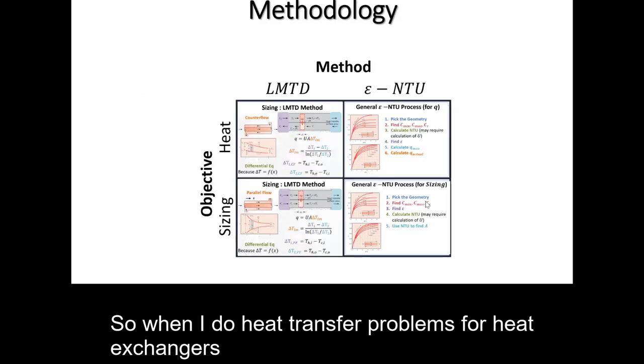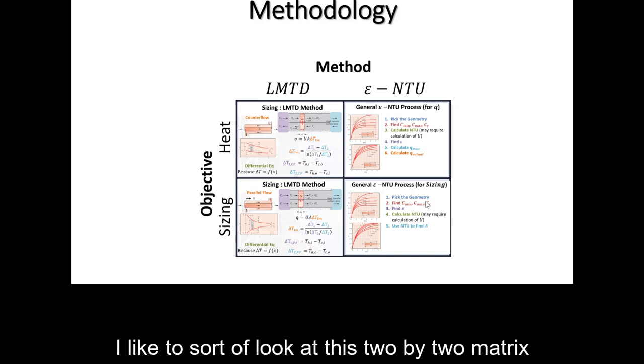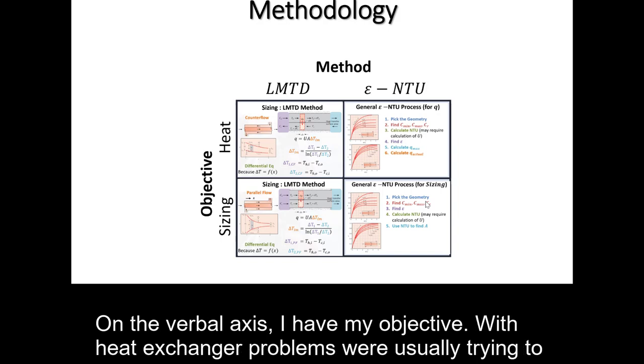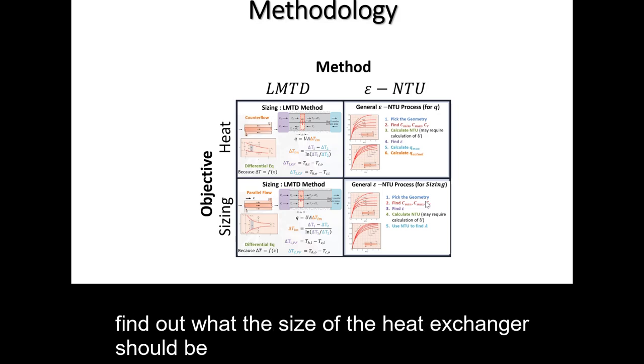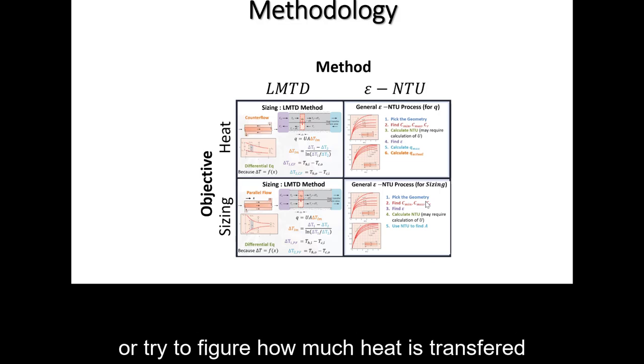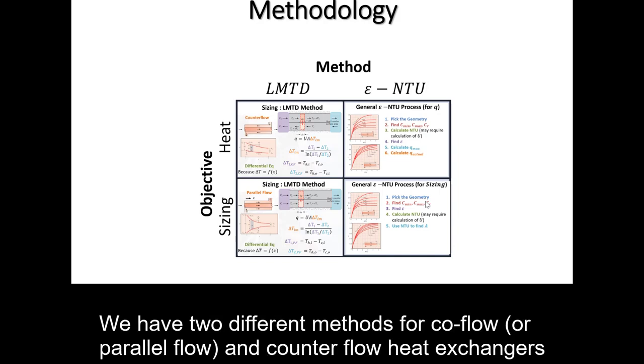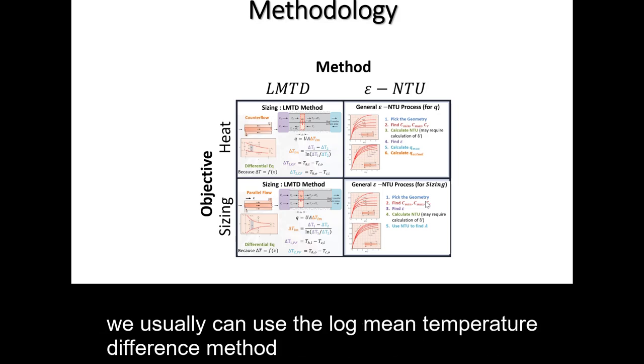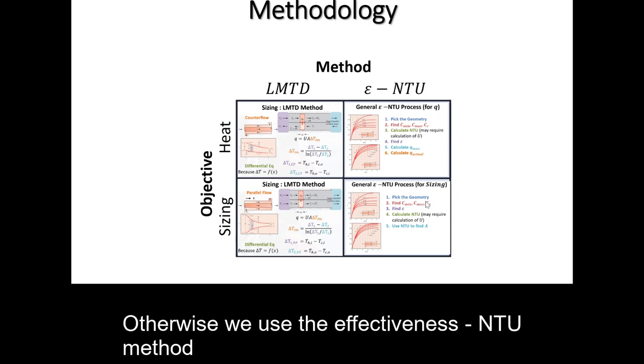So when I do heat transfer problems for heat exchangers, I like to sort of look at this 2x2 matrix. On the vertical axis, I have my objective. With heat exchanger problems, we're usually trying to find out what the size of the heat exchanger should be or trying to figure out how much heat is transferred. We have two different methods. For co-flow or parallel flow and counter flow heat exchangers, we usually can use the log mean temperature difference method. Otherwise, we use the effectiveness NTU method.